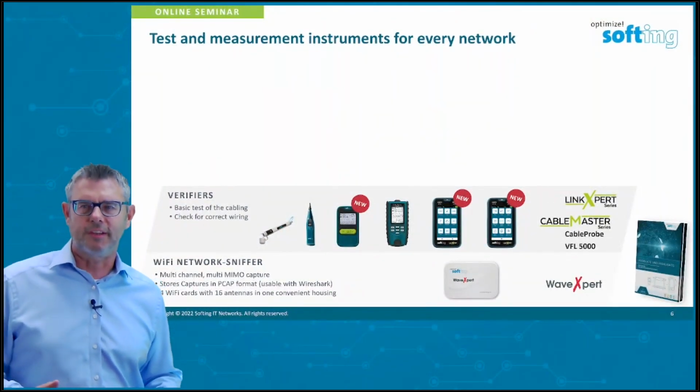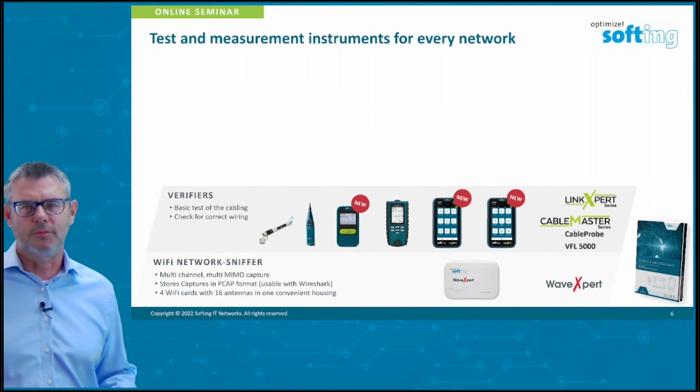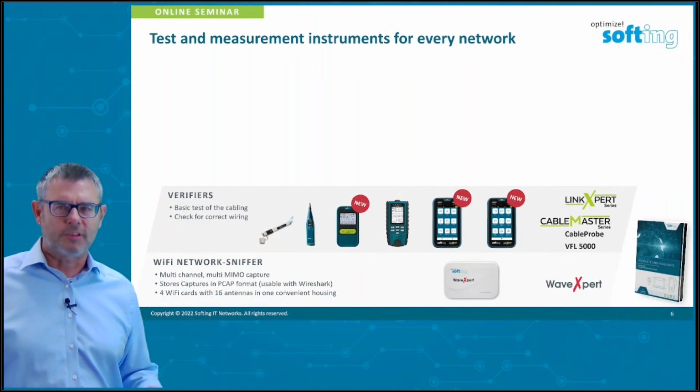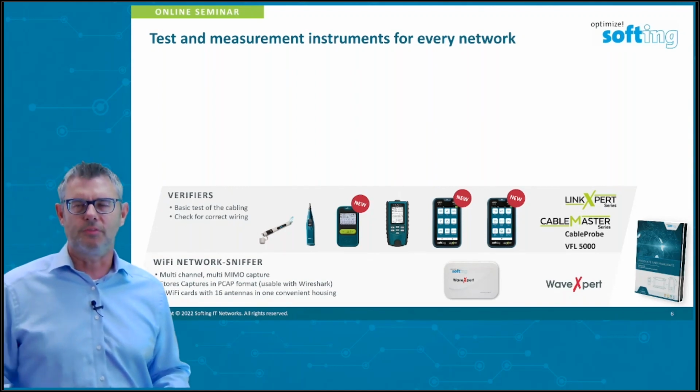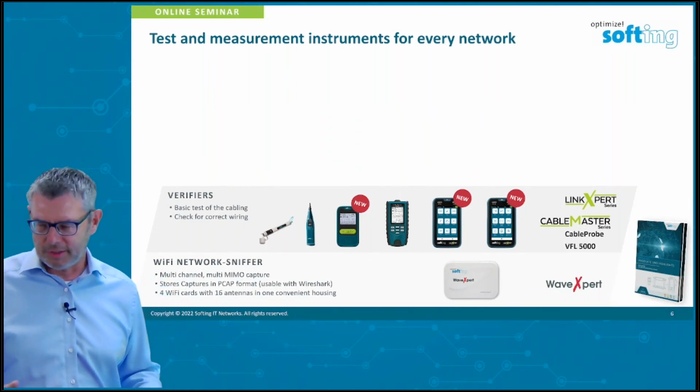Most of the instruments start at the verifier level. A verifier is just a very basic instrument, for example testing only wire map on a copper cable. So that's the level of wire verifiers or verifier instruments.